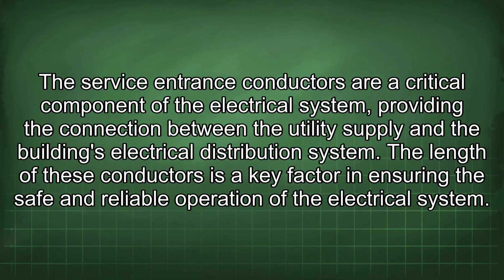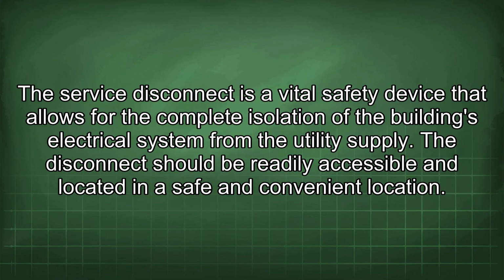The service entrance conductors are a critical component of the electrical system, providing the connection between the utility supply and the building's electrical distribution system. The length of these conductors is a key factor in ensuring the safe and reliable operation of the electrical system. The service disconnect is a vital safety device that allows for the complete isolation of the building's electrical system from the utility supply. The disconnect should be readily accessible and located in a safe and convenient location.